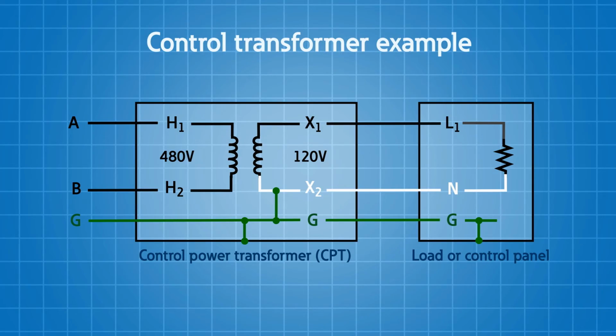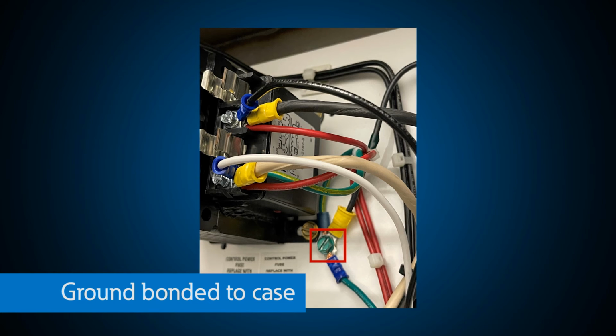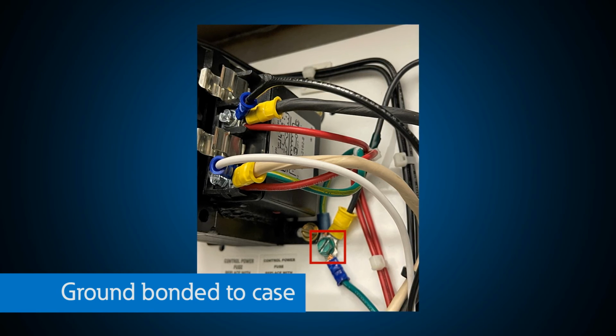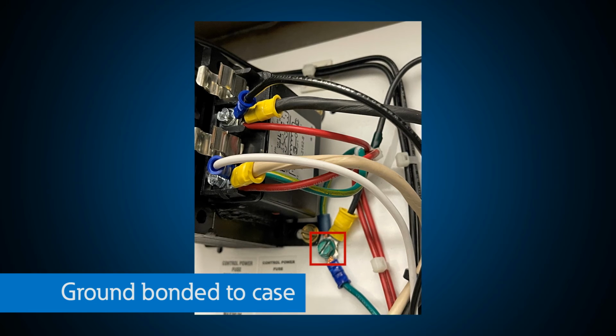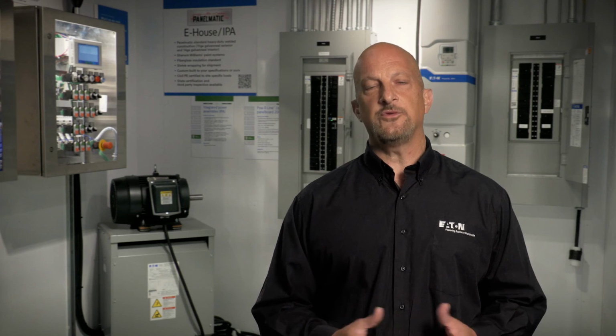This ground would also be bonded to the transformer case to ensure that the case and all metal parts remain at a constant potential for reference to the known ground conductor. I've seen many instances where this ground connection was not made, supposedly to make it better for power quality reasons, but it almost always made it worse, and electrical equipment was damaged.